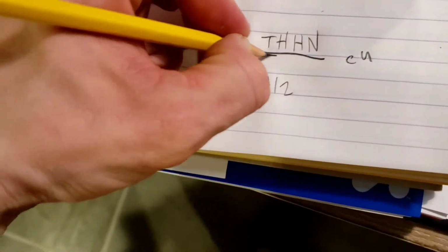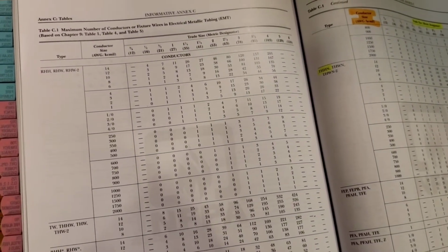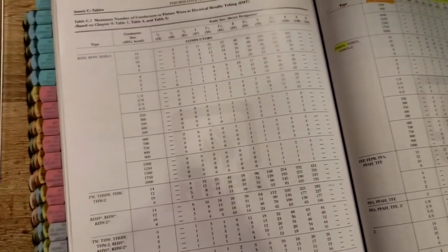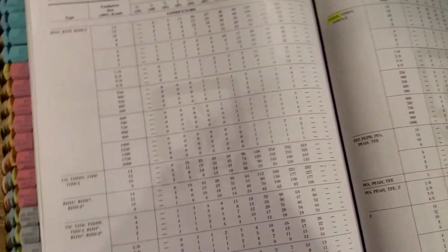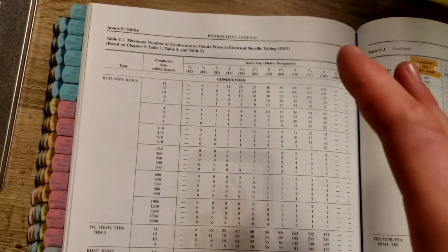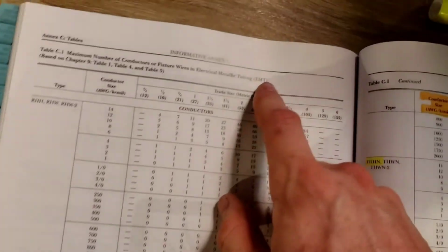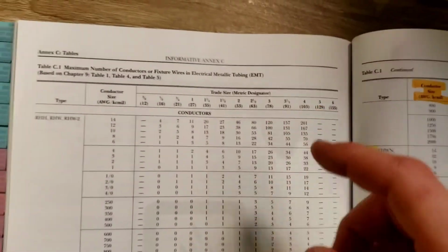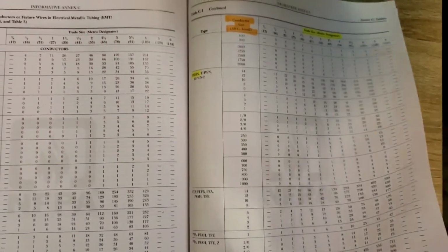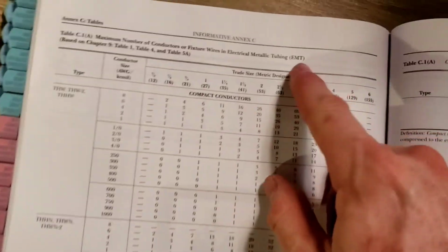So when you have that written out for you, you can just say, okay, well, it's 2.5 inch conduit size. Okay, and I hope right now you're wondering, does that fit every type of conduit? I hope I got you thinking a little bit. We just did EMT, so that's Annex C. That's just an example. But if you want to find your other types of conduit, you just got to flip over till the table ends, and you can find your other one.